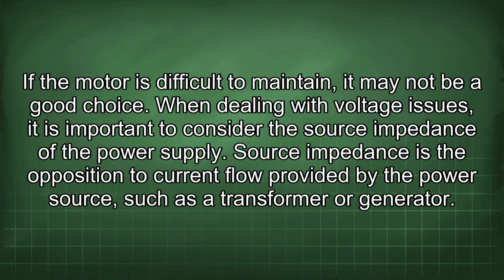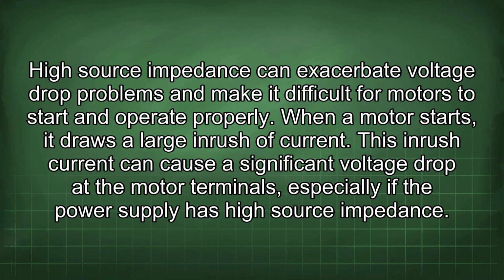Source impedance is the opposition to current flow provided by the power source, such as a transformer or generator. High source impedance can exacerbate voltage drop problems and make it difficult for motors to start and operate properly. When a motor starts, it draws a large inrush of current.